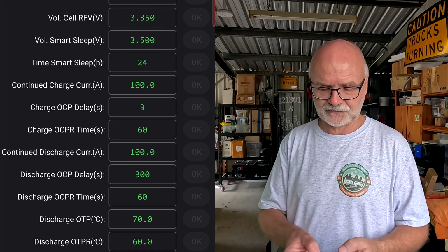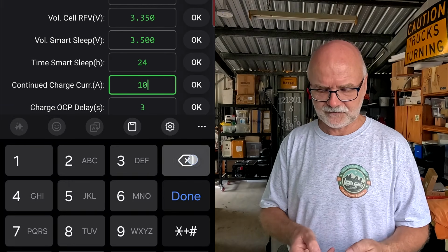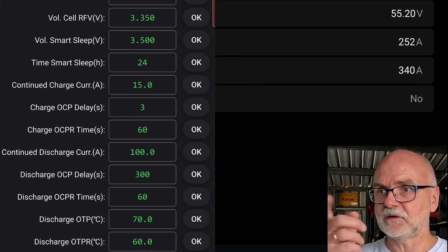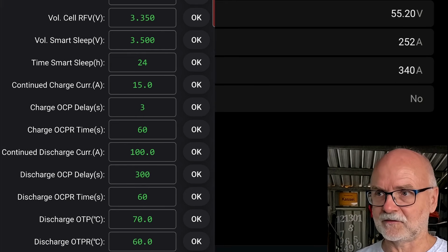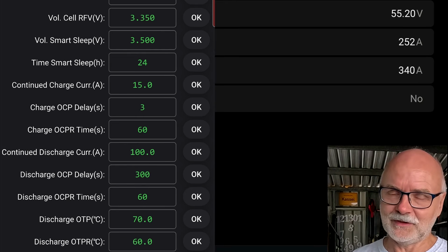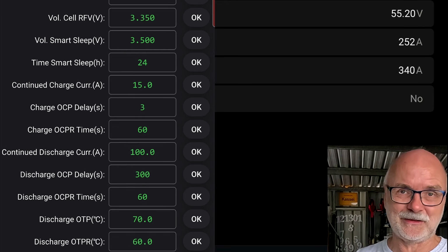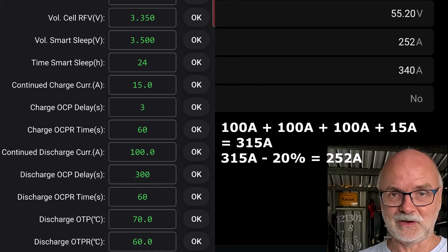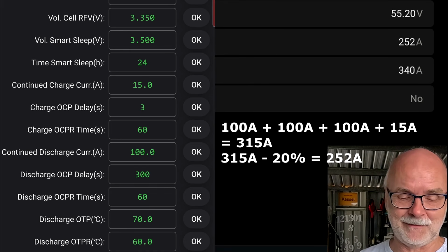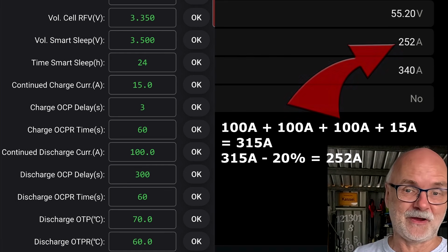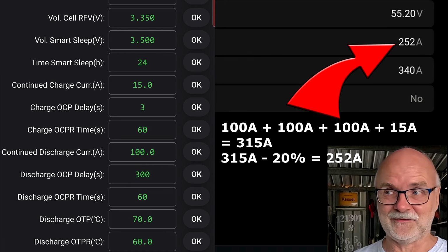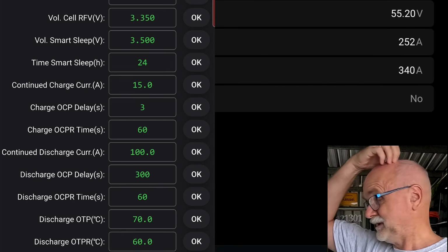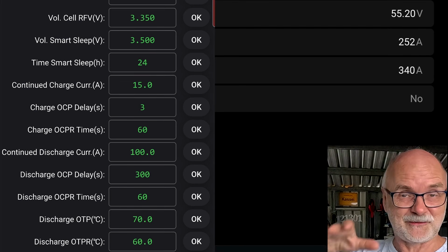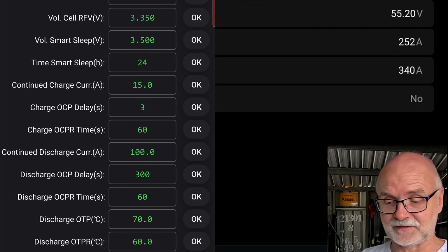I don't want to use 100 amps. Let's say 15 amps. This will obviously change our CCL here as well, because the master now realizes we've got 3 batteries sitting on 100 amps and only 1 battery is sitting on 15 amps. And it sums this all together and then takes 20% off basically. Okay, let me set something up to put a bit of current into this battery and then we can start the test.